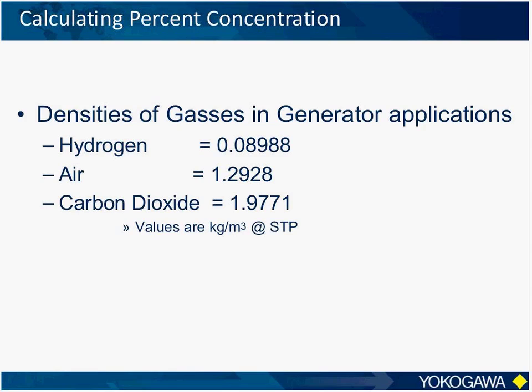Now, this is considered a binary gas application because only two gases are of concern at any one time. We would be concerned about hydrogen in air during normal operation, hydrogen in carbon dioxide during the first purge cycle, and air in carbon dioxide during the second purge cycle.